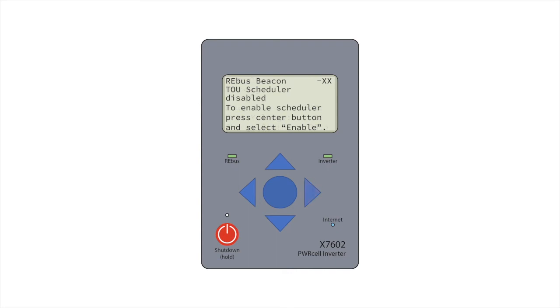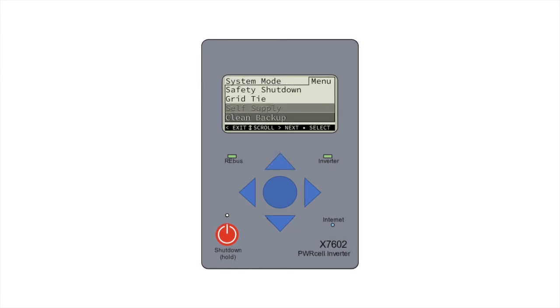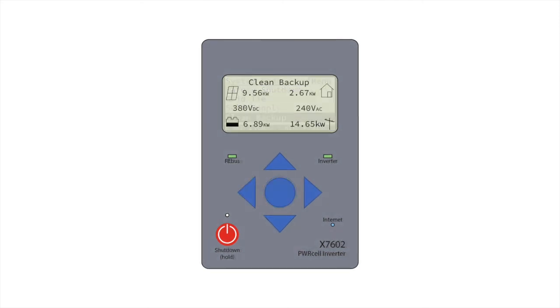Scroll to the right to return to the home screen where we can verify system production. You may also set the system mode now. For systems without a battery, we recommend grid tie. For systems with a battery, we recommend clean backup. See the Generac PWRcell Inverter Owner's Manual for more information on system mode options.